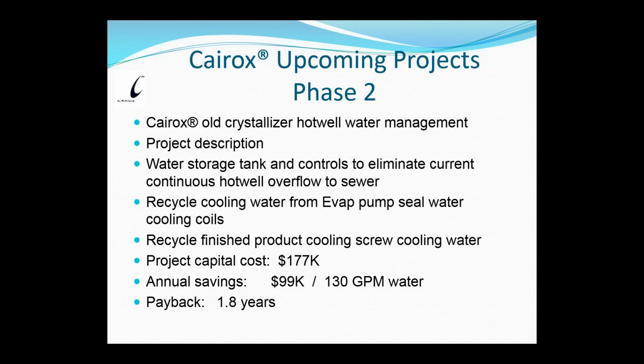And then we also have mechanical seals on a lot of our pumps, and we have a cooling pot on those mechanical seals. So we basically have water going through a coil that's in a little pressurized pot that cools the water off as it goes to the mechanical seal and back. So that water was just going to the sewer also. Well, I'm going to now send that back to this. So the total amount of water saved is 130 gallons a minute, which equates to $99,000 a year of savings. The project capital cost right now, I put at $177,000 to do, which I've already got all the quotes and everything done for it. It's ready to go.